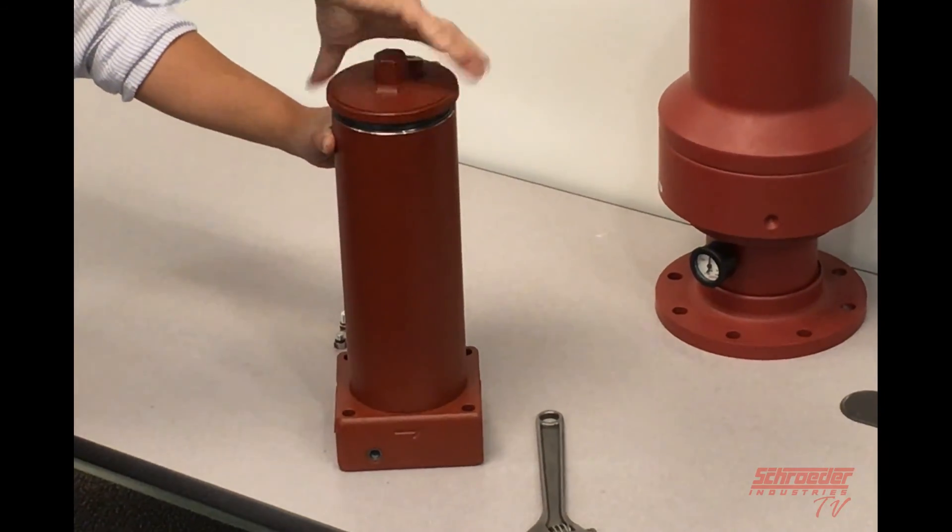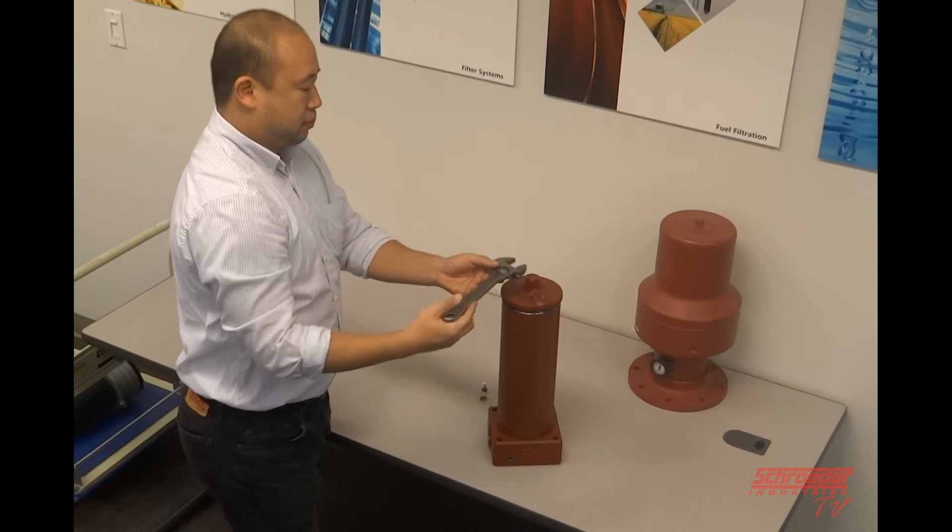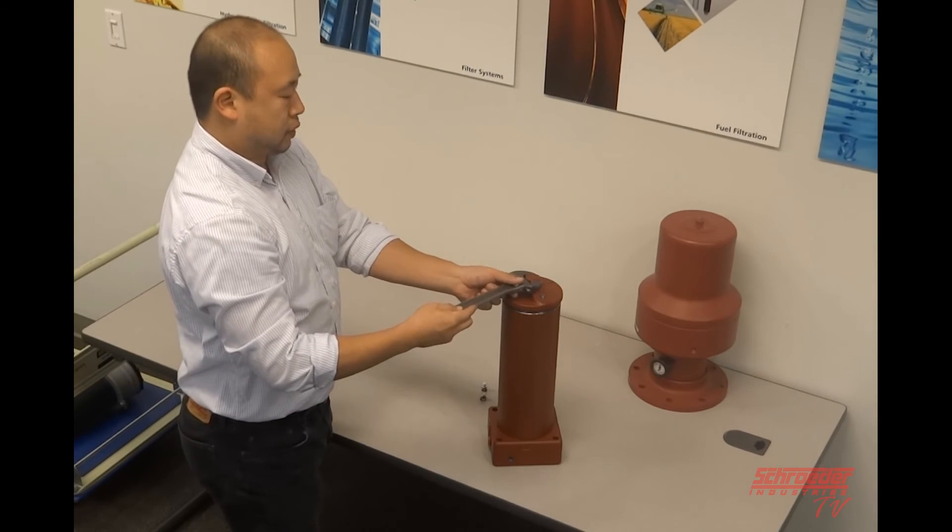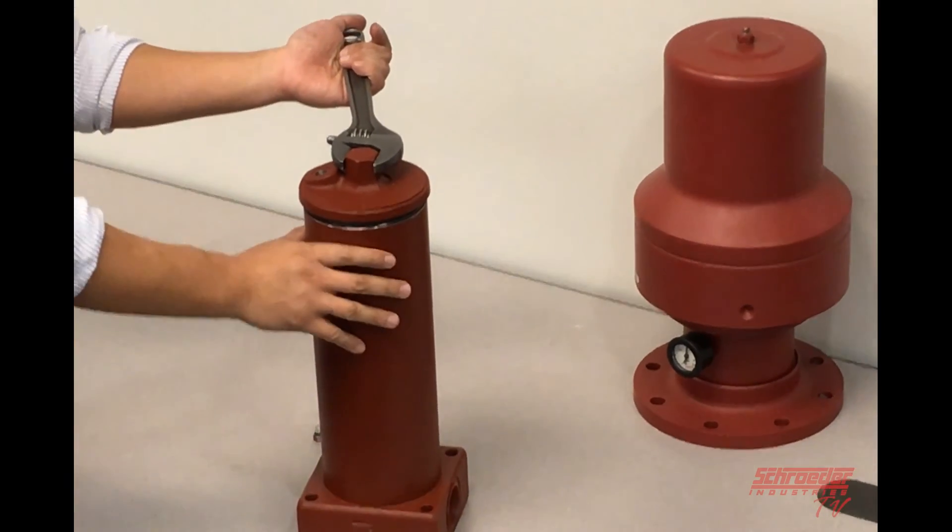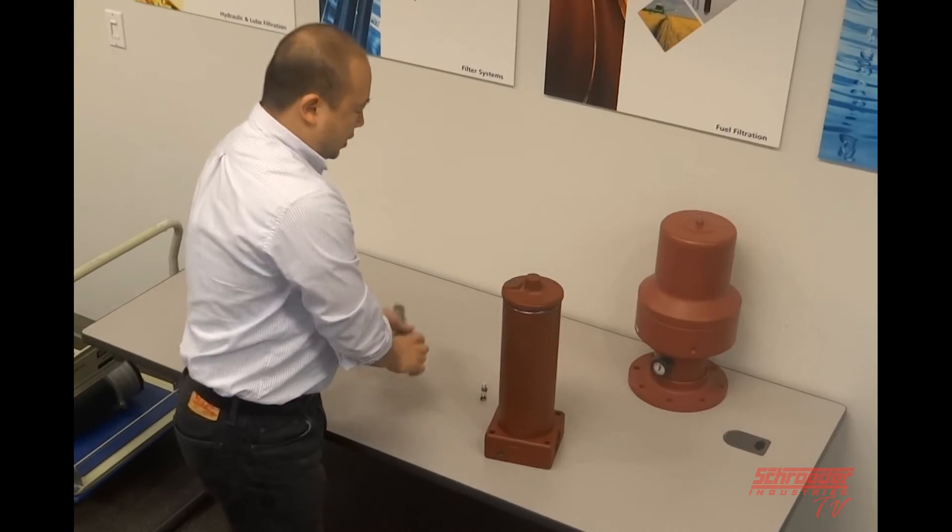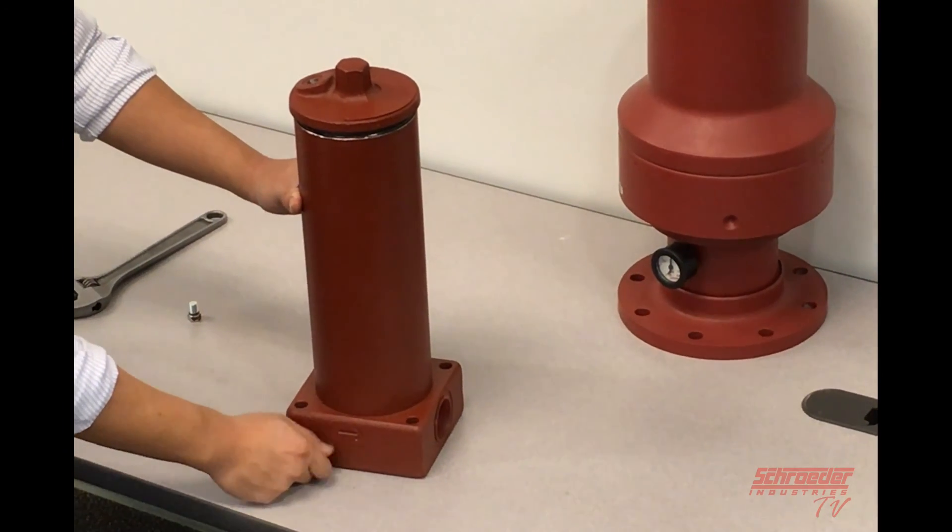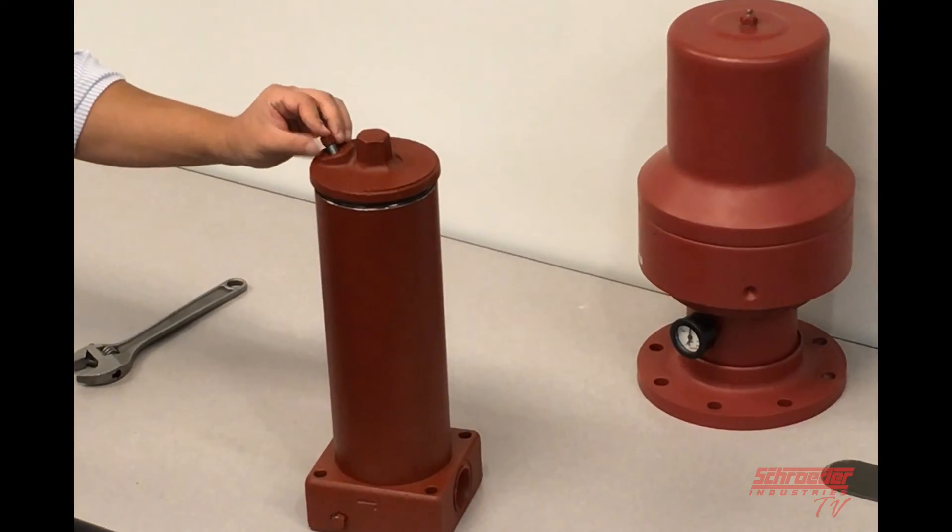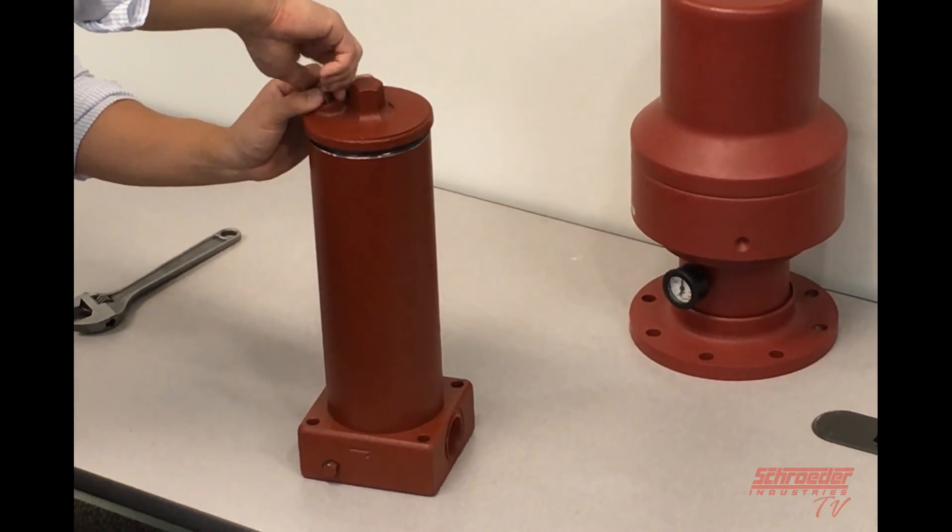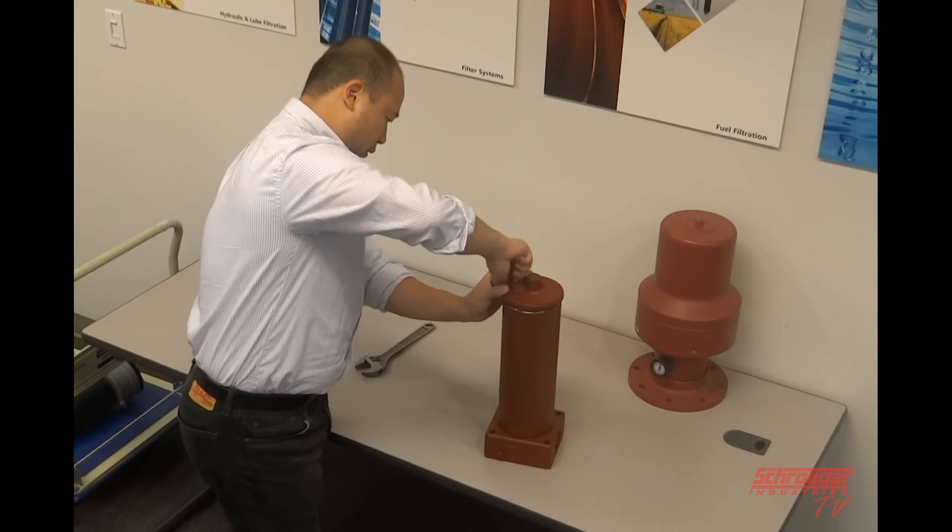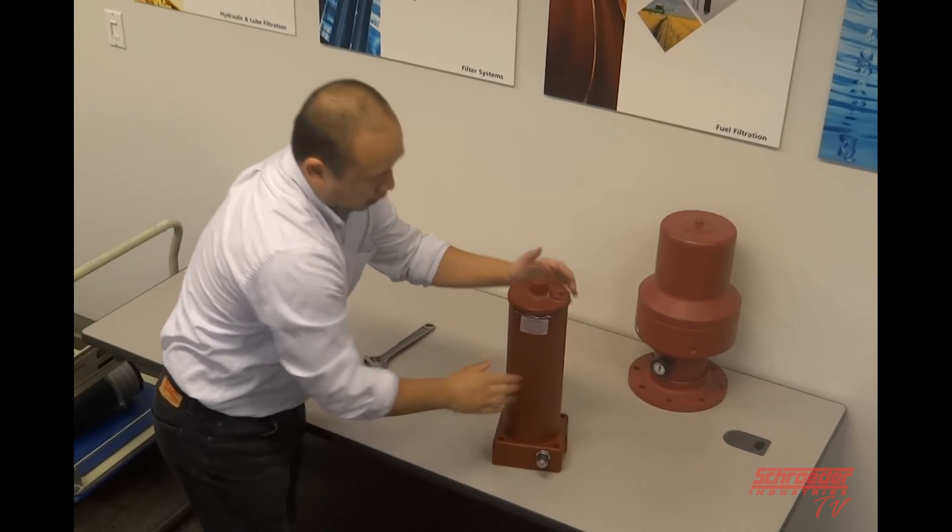And we replace the cap of the housing. And again, it depends on the customer. The pressure for the cap may be different. Usually it's 100 pounds, but it could be more. Or it could be less, depends on the application. So you just want to use a torque wrench to make sure that the pressure is accurate. So once that's tightened down, we want to replace the drain plug and then the bleed plug. And then we connect the inlet and outlet back in and the element is changed.